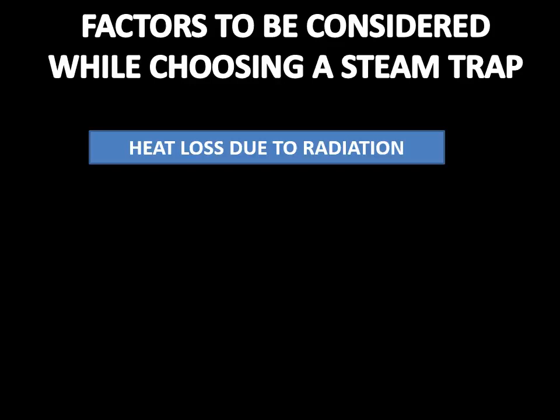Consequently, larger amount of heat will be lost due to radiation. Because of that, the bucket type steam traps are somewhat inferior to the thermodynamic steam traps because of the larger area of bucket type steam traps.